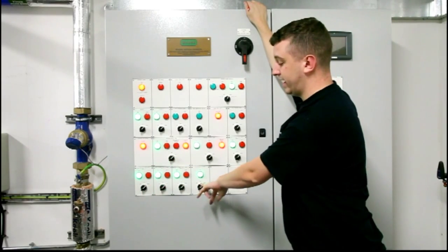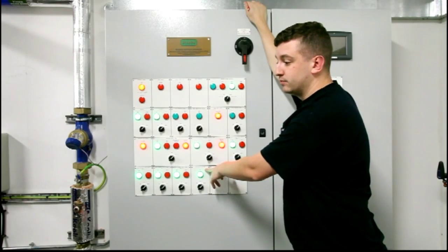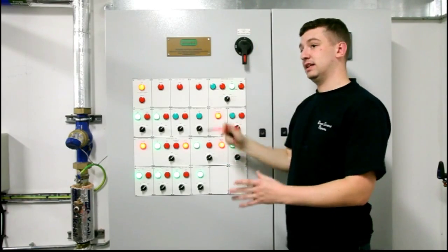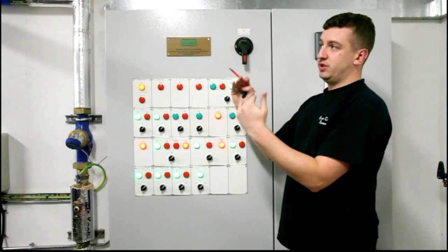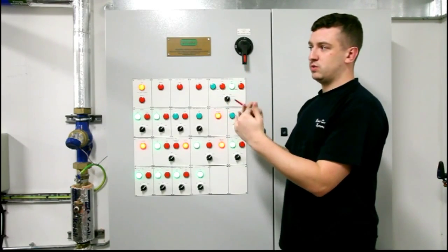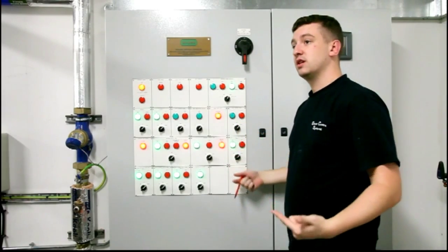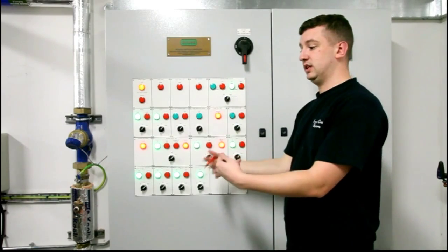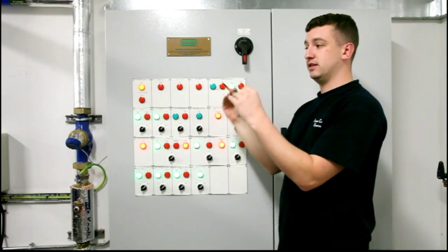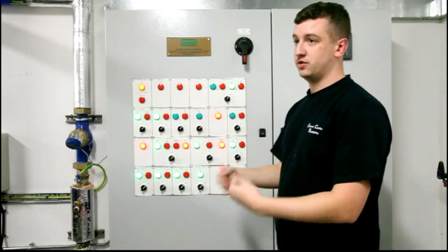And then we've got a convector heater, which again is in the kitchen. We've got a stat in the convector heater, which just means that whenever the temperature in there drops below, I think it's 21 degrees, we'll just turn on the convector heater to give it some heat. Just blast some heat to the kitchen until the return air stat is at 21 again, at which time we'll just turn it off. So it's just run like that.